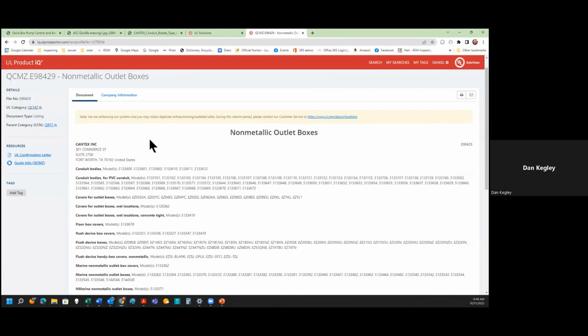And I just put in the company name to narrow it down from the 8,000. So I got to the company name, Cantex, the category number, and the heading is non-metallic outlet boxes, but that's just the heading. If you read further into it, it says conduit bodies for PVC conduits, and you can find the model number of the particular LB that we were just talking about right there. So this is the UL listing for it, to say what it's actually in there for. And then when you drill down into it further, it'll give you the details of what the conduit body has been tested for.